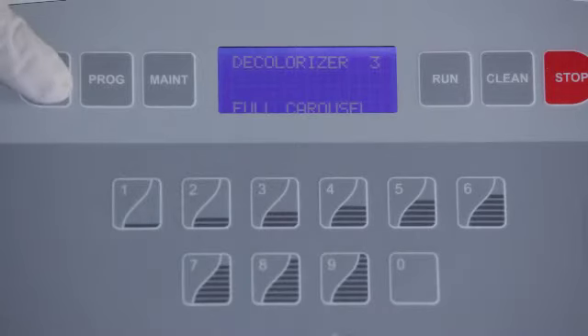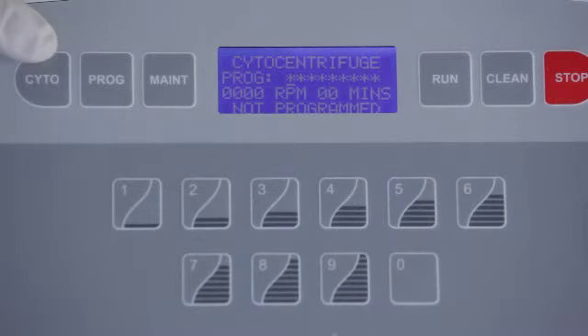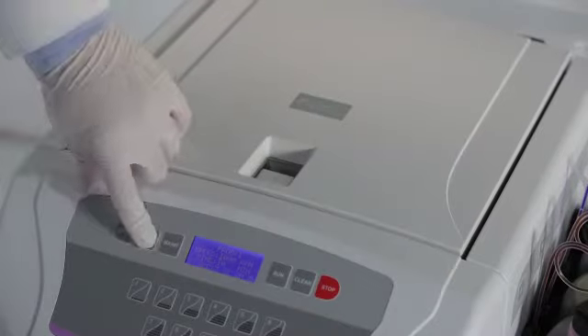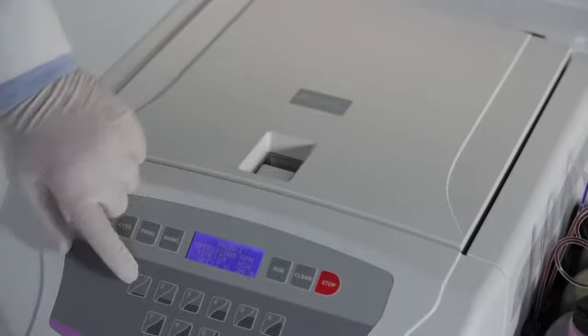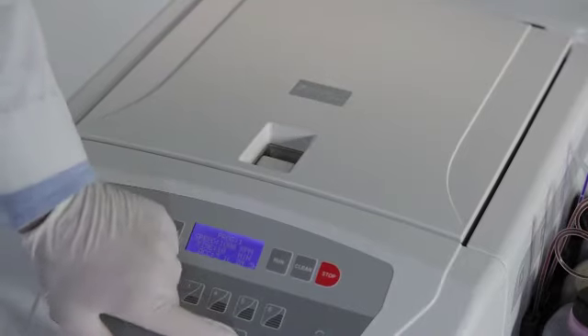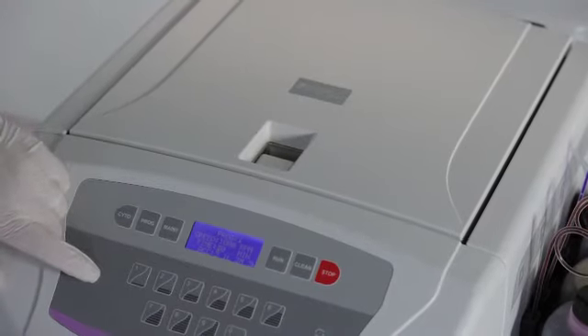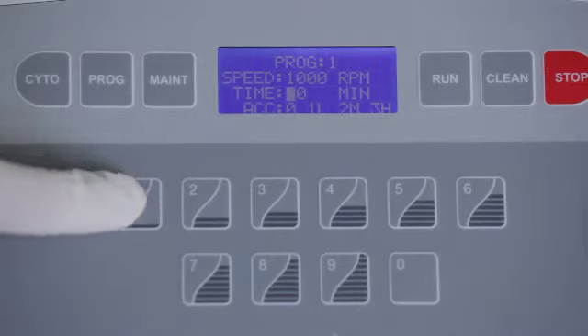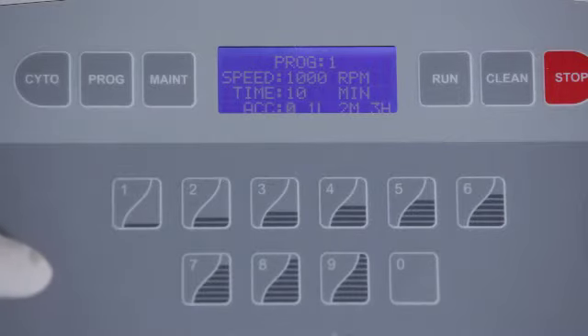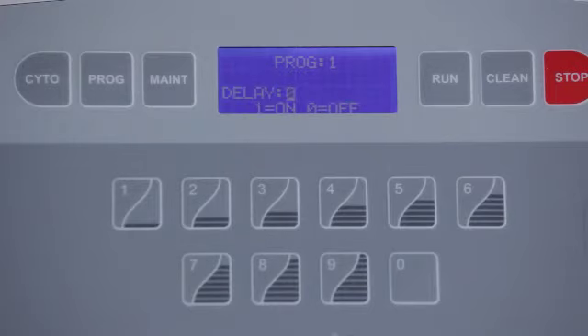The cytocentrifuge function of the stainer is activated by pressing Cyto. The speed, time, and acceleration can be set by pressing Prog. Speed is set by typing in the desired numbers. The last digit cannot be set, so the cursor automatically drops down to the time after the speed is set. Set the time and acceleration. Most samples are run with the high acceleration.